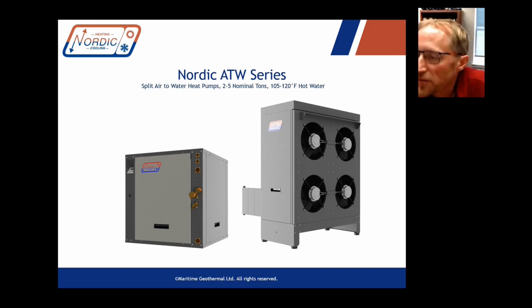One important thing to mention about our air to water system is that it's a split system. If you find other air to water heat pumps on the market, they're likely to be monoblocks. That's the way most people are making them. So that is a single unit which sits outside. It doesn't make sense to us for a cold climate to have your hydronic water from your in-floor system or your domestic water going into the cold to get heated. So it makes sense to us to have a split system where our compressor and electronics and refrigerant to water heat exchanger are all in the indoor unit, and the only thing in the outdoor unit are the refrigerant to air heat exchanger and the fans.